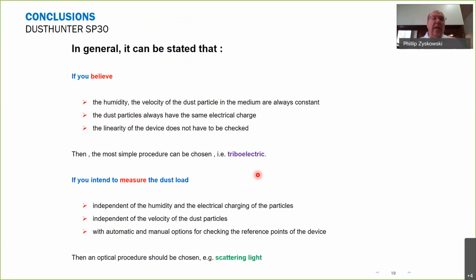So again, if your application and installation is always constant, and the dust particles are always charged the same, and if you don't need linearity, then triboelectric flow would be the way to go. You're just looking for some basic indication, a very wide, roughly measured trend. If you really need to measure your dust load, independent of those items and those factors, then scattered light is the way to go.